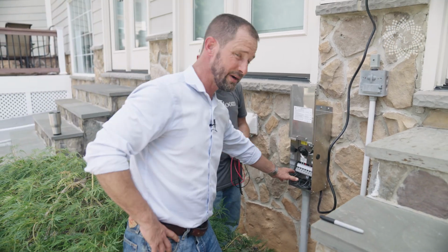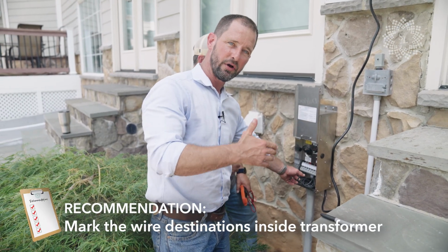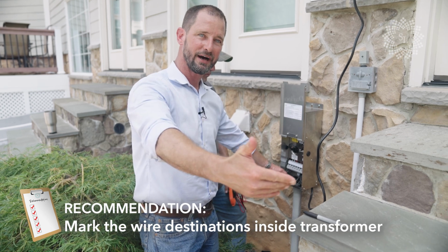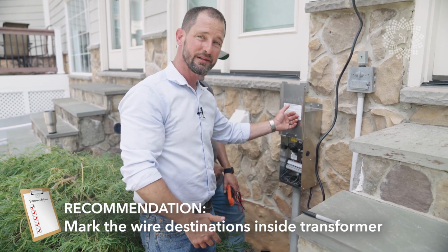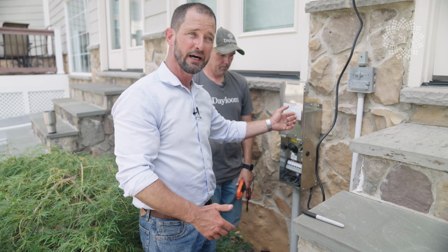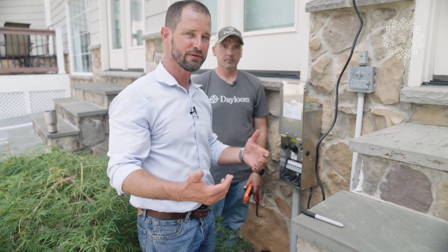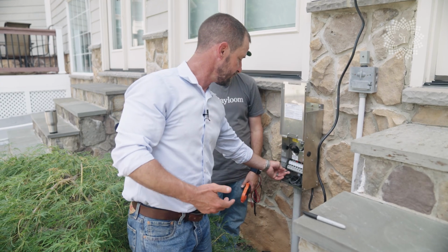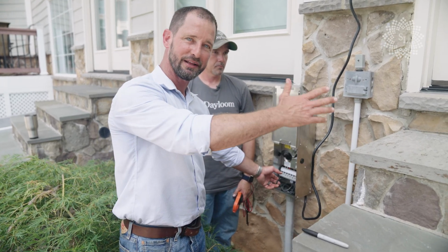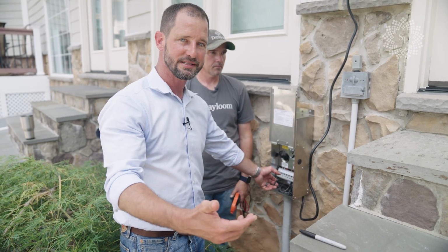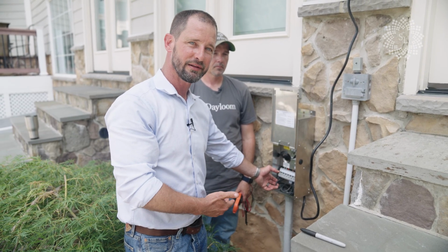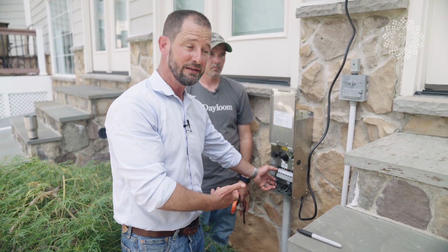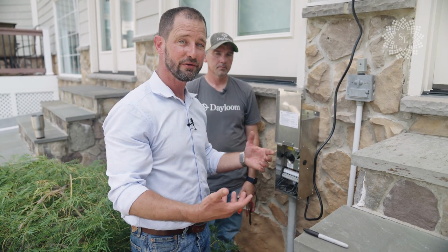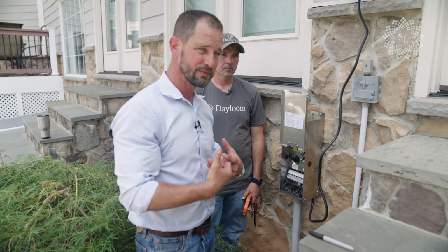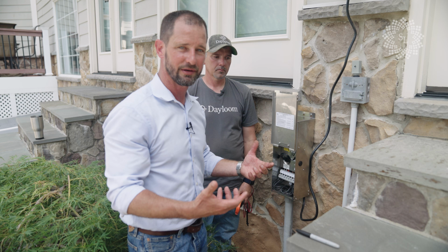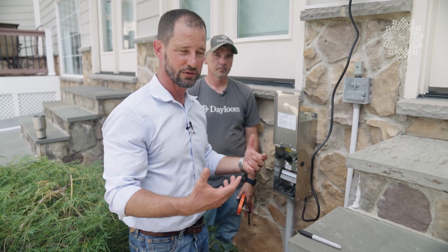And what we like to do is mark the wires now, mark to where they're going to go. So this wire is controlling 5 lights over here. I like to put it in the transformer and have that all set on there. The other thing is you mark the amperage. So if you ever come back for a service call 5 years later, someone could look and see this wire here is controlling 5 lights on the left side of the house, and the amperage was 3.87. If somebody comes back later and they put the amp meter on it, and it's at 12, either there's some type of short happening or somebody added lights to the system. And in our systems, we don't like people adding lights to it because they're not typically verifying any of this, and they overload circuits and overload transformers.